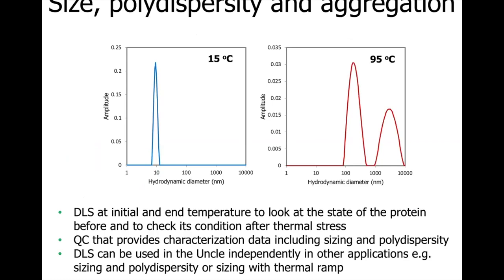In the Tm and Tagg application, DLS is performed at the start and end temperature of the thermal ramp. The DLS at the initial temperature allows us to check the condition of the sample prior to thermal stress and see whether the sample is monodisperse and of good quality or already contains aggregates. The DLS at the end temperature gives information about the state of the protein after thermal stress, with both sizing and polydispersity data available. Because DLS is a non-destructive technique, this is a quick QC step done on the exact same sample that provides complementary information to fluorescence and SLS data.